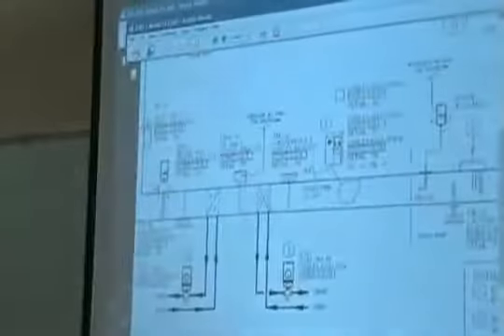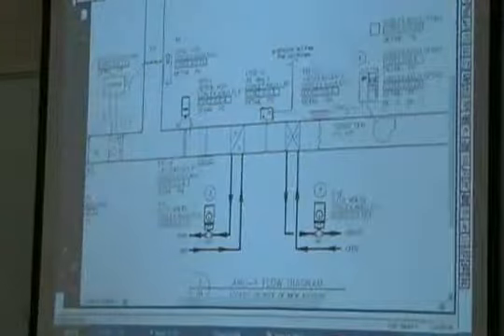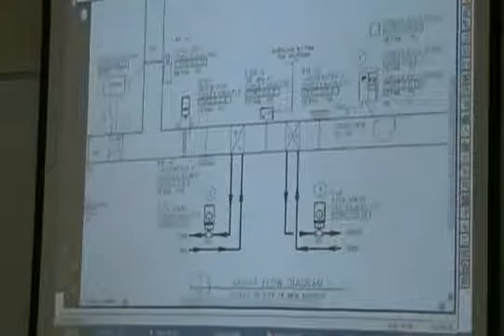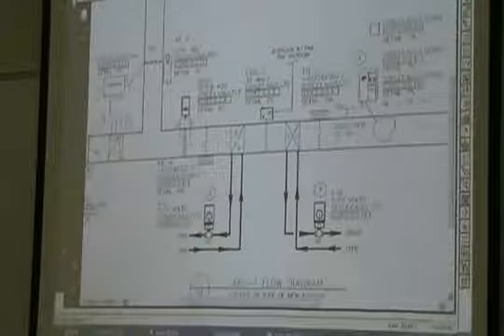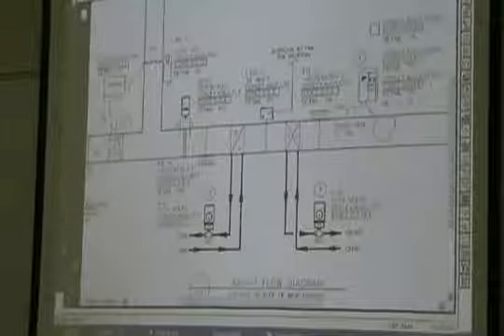Okay, we kind of talked about the economizer control already, but it says here that if it's less than the changeover set point, and we discussed how you come up with that set point, then the outdoor air damper shall modulate the airflow between the minimum required outdoor airflow set point and a full open position to maintain the discharge air temperature. So on this one, if we're using outdoor air, it's going to modulate this outdoor air damper to maintain the supply air temperature. Instead of maintaining the mixed air temp, it says that it wants to actually maintain the discharge air temperature set point. Okay, so that's going to be in sequence with the chill water valve. You don't want both of them working. Until that outdoor air damper gets wide open, then the chill water valve would open up.